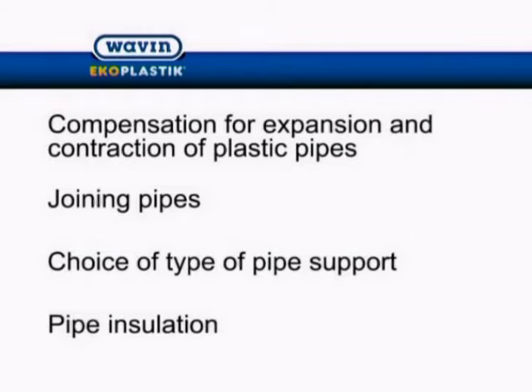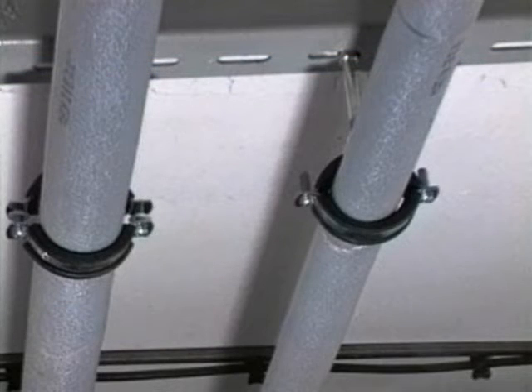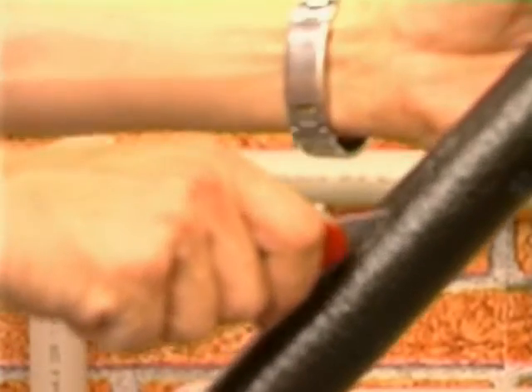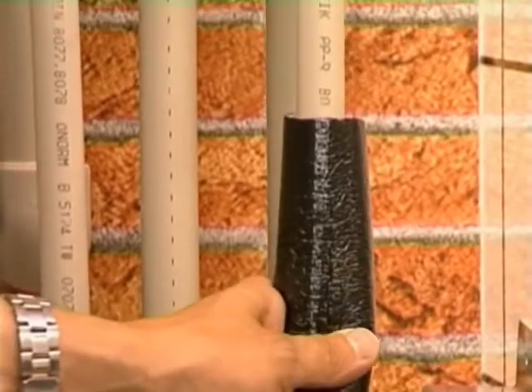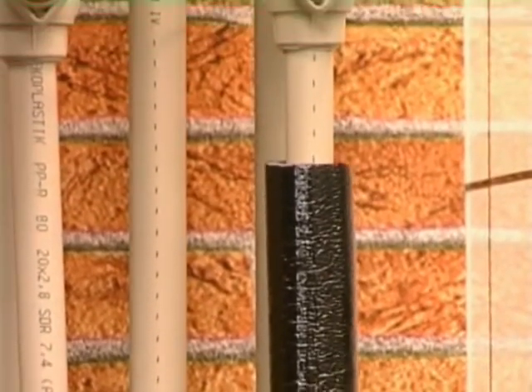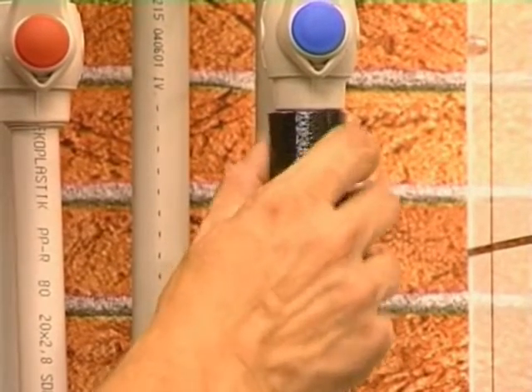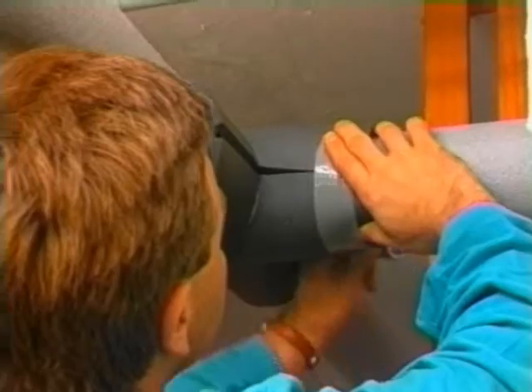Pipe systems should be insulated throughout their length. Insulation is carried out after a successful pressure test. Cold water pipes are insulated against condensation and hot pipes against heat losses. The most commonly used type of insulation is slit polythene foam tubing. This can be fitted around the pipe or cut to fit round welded sections and joints. The recommended thickness of insulation is given for all sections of the water system on the basis of evaluated heat gains and losses.